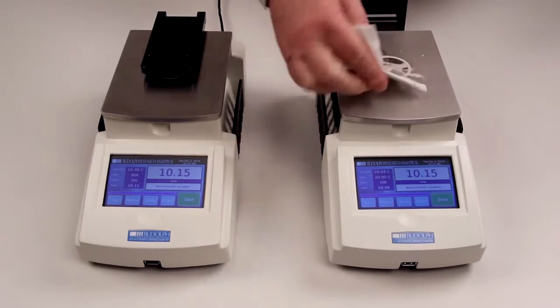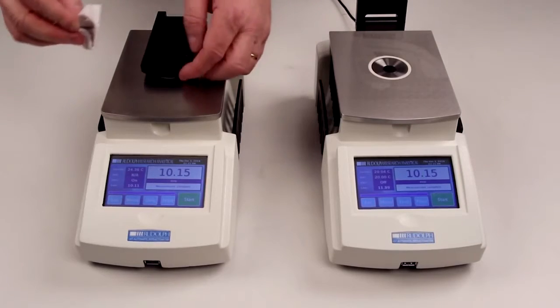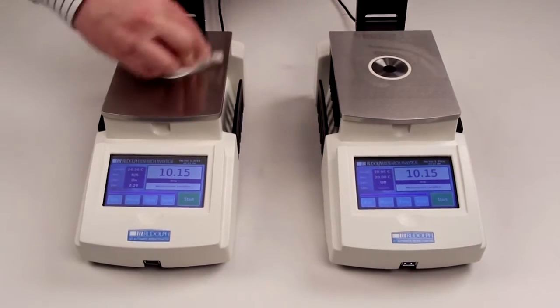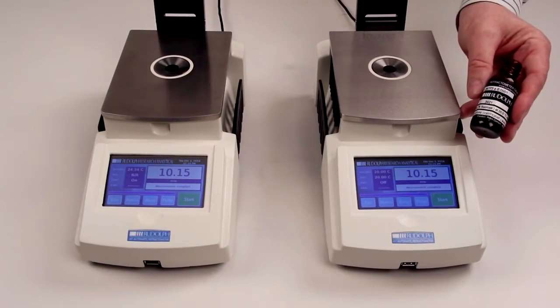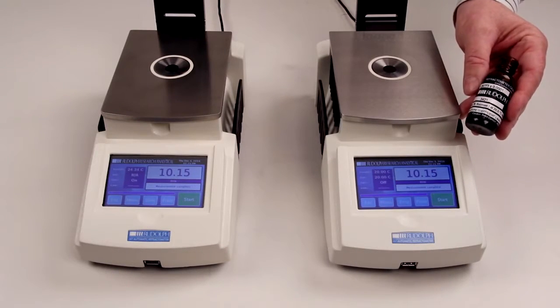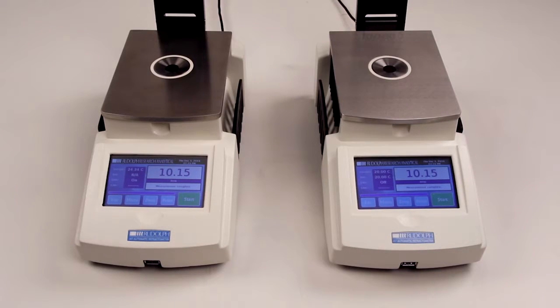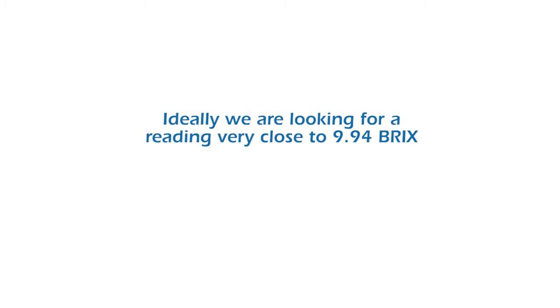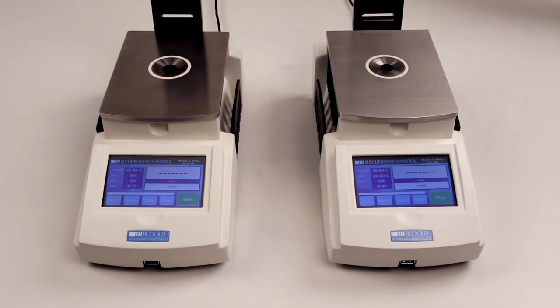However, let's imagine now that our factory is ISO certified. In a situation like this, all instruments would need to be regularly calibrated back to a traceable standard. What I have here is a calibration standard traceable to NIST. While different countries will each have different authorities to answer to, using a traceable standard will always be a component of remaining in compliance. In addition, the calibration standard will not be sugar and water-based, as these are not stable over time. In this case, the standard we will use should measure very close to 9.94 Brix. Thus, if the refractometer measures this correctly, it proves the refractometer is properly calibrated and within specifications.